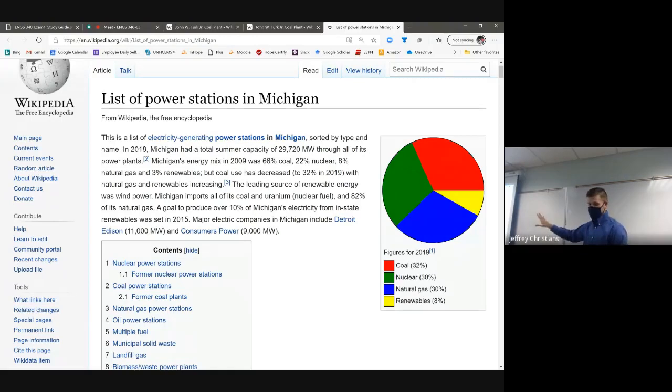About a third of it comes from natural gas, which again uses the same cycle, the same pressures, and has the same limitations. We still have to use 500, 600 degrees Celsius. We can't go too much above 20 or 30 megapascals. We can't go too much above 40% efficiency. We're kind of stuck in the same region. They operate exactly the same. They have a different heat source, nuclear fuel instead of coal, but it's the same. We get stuck in the same world for the same reasons.